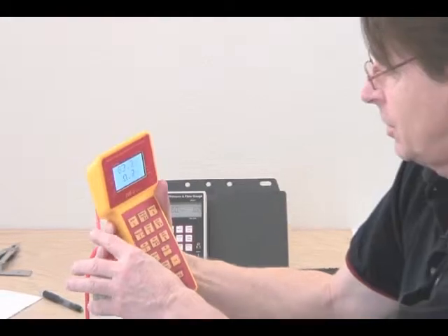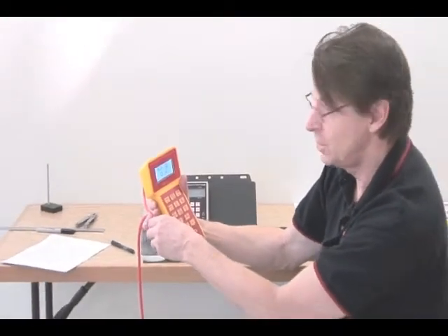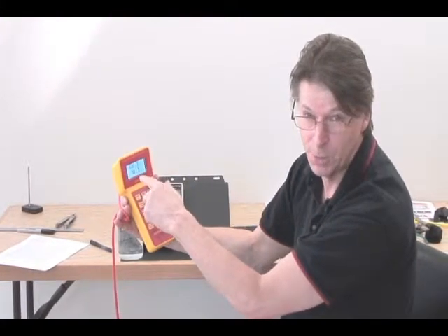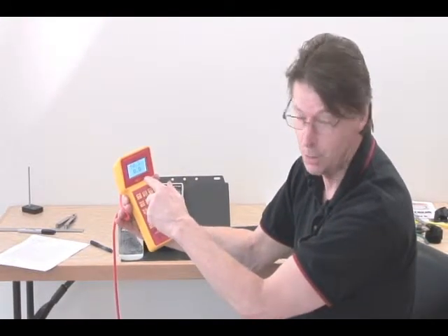So that's critical. The other thing that can happen is if our tube is pinched and we plug it into the gauge, right away we'll see a big positive pressure. And if we see that, we know we have a pinched tube problem.